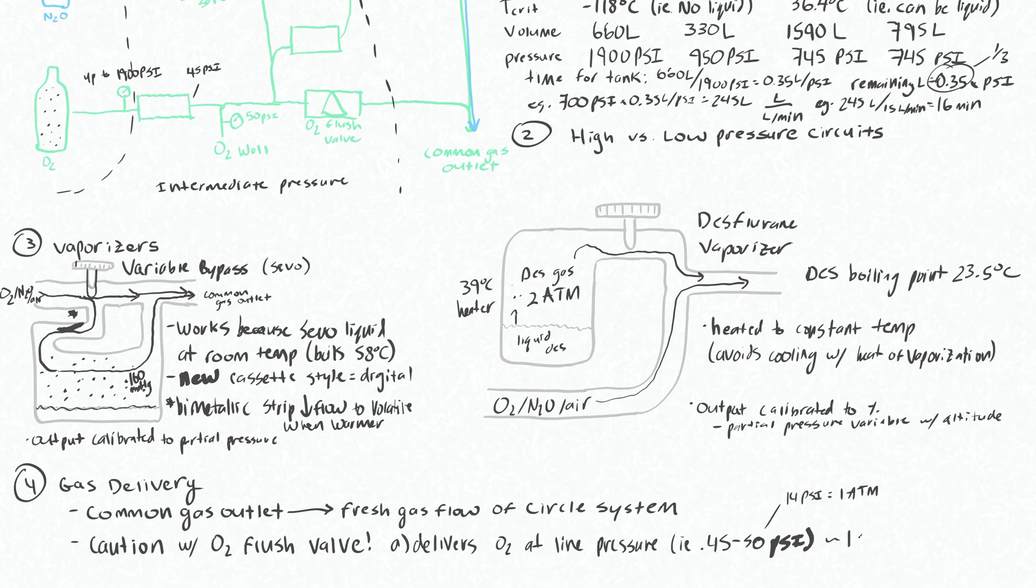This can equate to flows of about one liter per second. Just imagine the damage this would cause to somebody's lungs if you were actually giving them one liter every second into their lungs that that button is depressed.